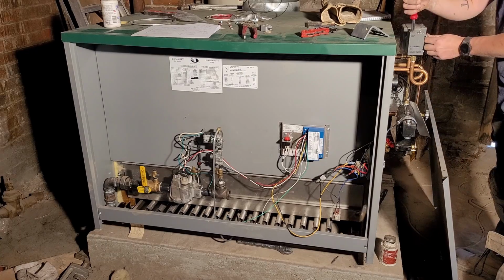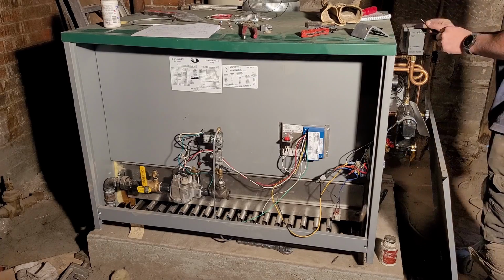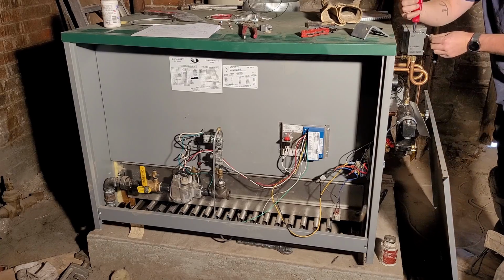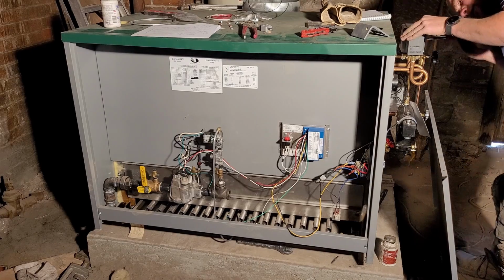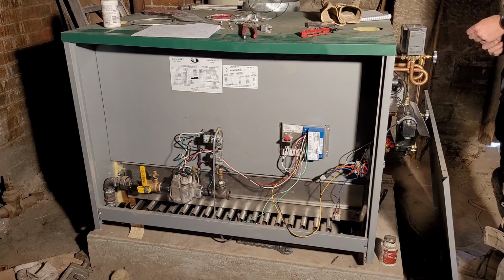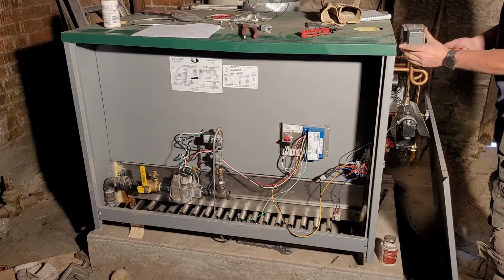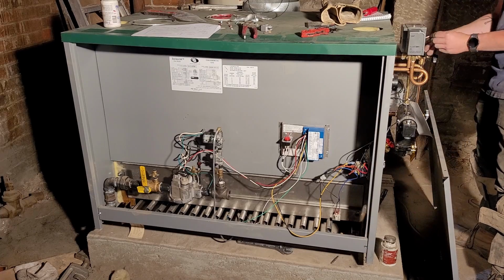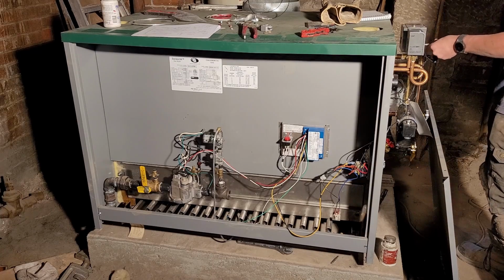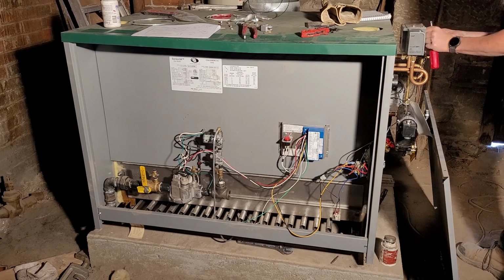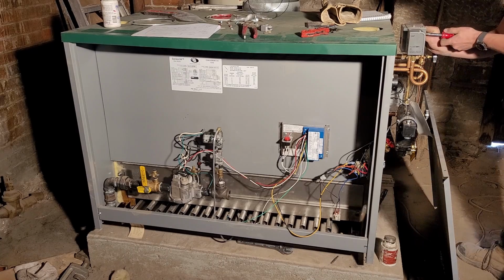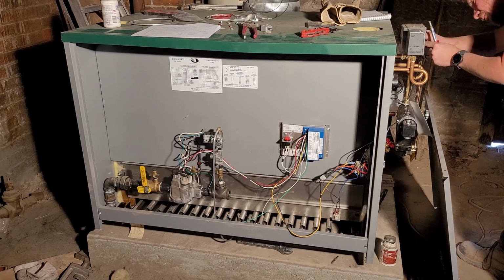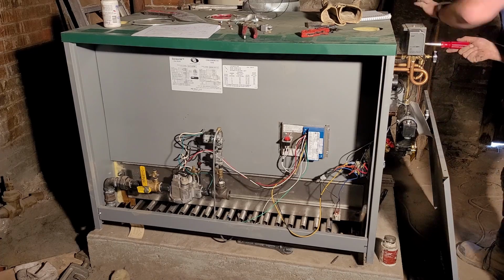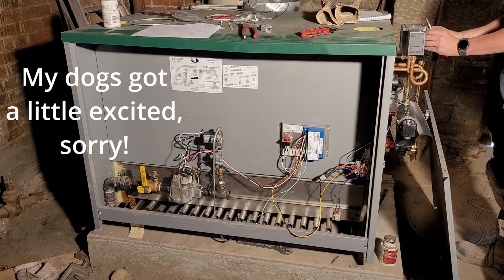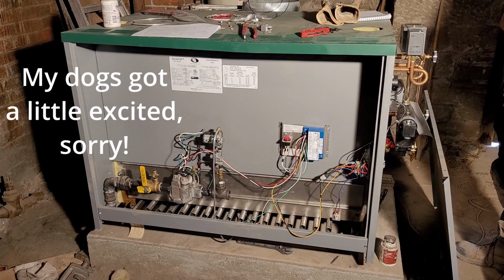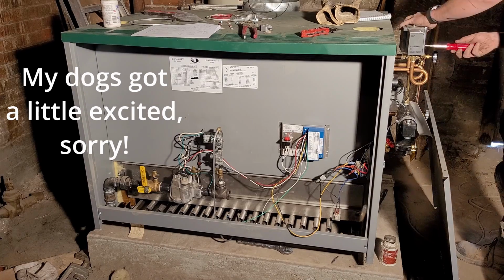I'm not going to tie any of my wires up into their final positions and put zip ties on them until I actually fire the boiler and make sure that it's all working. Because if there is something wrong, say there's a nick in a wire I have to repair, it's a lot easier as it is now when it's all loose and open, where I can quickly make a repair if I need to. So that will look kind of messy until it's all actually ready to go. But yeah, I think that's it.